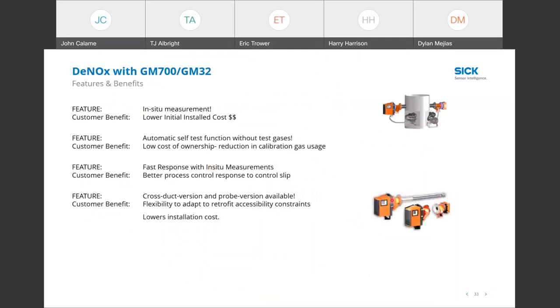So as Dylan was talking about, this is the single probe design, and then this is a cross duct. So depending upon your application, your ranges, and also physical constraints of where you're mounting the device and where you have access, would determine which one of these you use. Both would work, but one may work better for you. You may have access on only one side of the device, as far as platforms, and it might be more beneficial to put the single probe in. Single probe usually is easier to put in because it's only got one little connection. But if the application dictates as far as the range, and we need to get a larger optical path, that might be one reason for going for the cross duct.